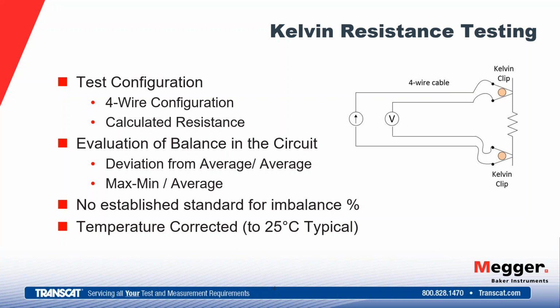There's actually no established standard for what that imbalance should be. It may differ a bit from switchgear to the motor itself. In fact, we're evaluating some different things there. If we're testing from switchgear, then we're going to assume that our imbalance is in that junction box. So we're going to go down and visit the junction box, open it up, and check our connections there, looking for any kind of corrosion or loose connections.